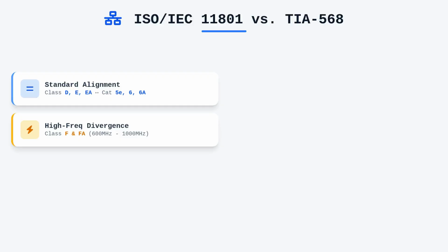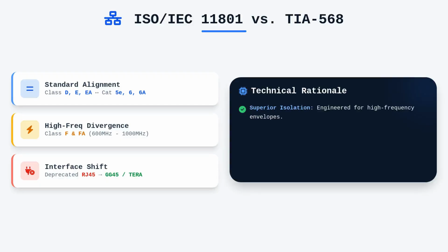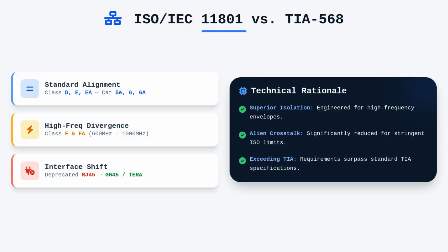We must look closely at how Class D, E, EA, F, and FA correspond to their TIA counterparts, while noting the specific technical divergence, where TIA 568 uses categories 5E, 6, and 6A, ISO IEC 11801 uses Class D, E, and EA to describe similar frequency envelopes. However, the divergence thickens when we reach Class F and Class FA, which encompass frequencies up to 600 MHz and 1000 MHz respectively. These classes effectively deprecate the RJ45 interface in favor of non-RJ45 connectors such as the GG45 or Tera interfaces. These connectors were specifically engineered to provide superior isolation and reduced alien crosstalk, which is a necessity when testing to the more stringent ISO IEC limits that often exceed standard TIA requirements.